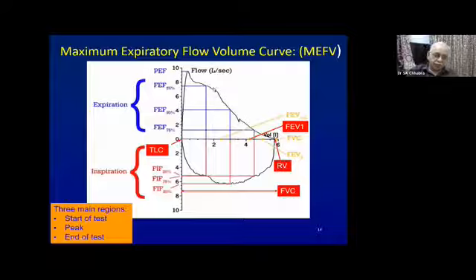Now, an important physiological point to know is that the first one-third of the expiratory flow volume curve is effort dependent. That is, if the patient's efforts are not uniform or reproducible, then the peaks can differ. But the latter two-thirds is reproducible. So irrespective of the patient's effort, the curves will fall along the same line in the latter part of the curve, which makes it very reproducible. So these are the different parameters that we measure.